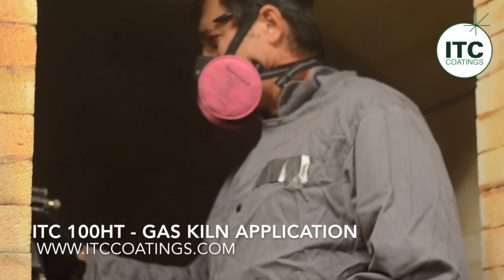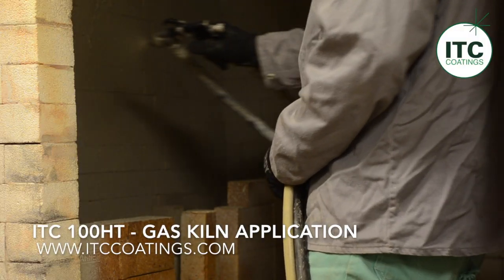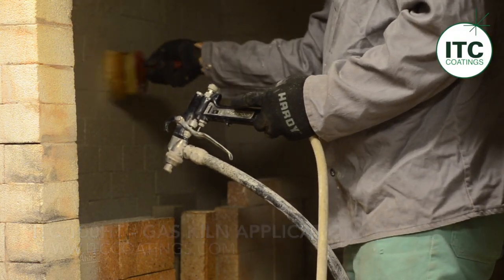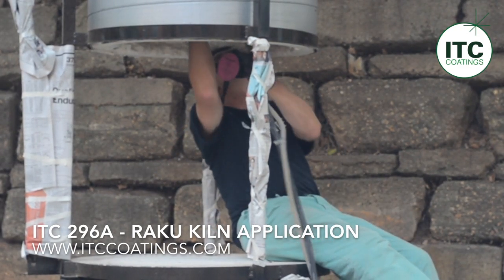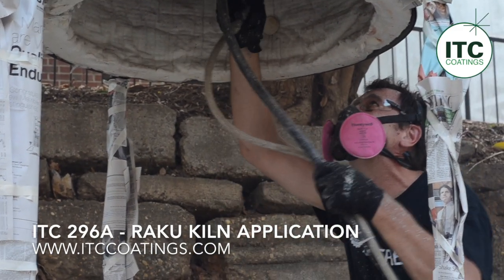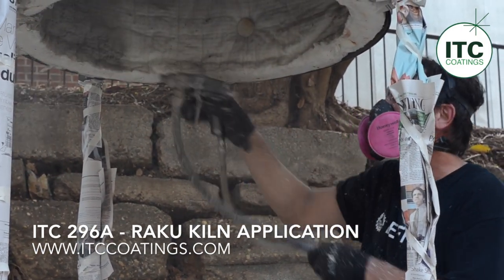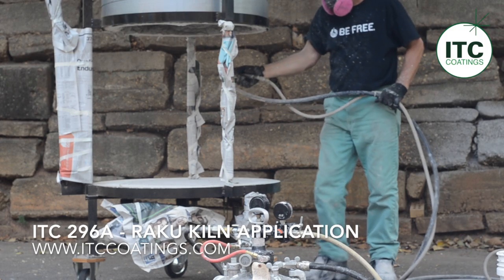The preferred method of application is to spray the coatings onto the substrate using a commercially available textured drywall hopper spray gun. In the application shown here in this video, I am using a Binks two-gallon pressure pot spraying rig. Square-foot coverage rates are 50 to 100 square feet per gallon of ITC 100HT and 100 to 200 square feet per gallon of ITC 296A. Once cured, ITC products produce a very hard protective surface over soft friable refractories such as insulating firebricks, IFBs, and ceramic fiber blankets. ITC coatings produce cleaner operating environments in kilns and furnaces, resulting in higher temperatures, lower fuel consumption, and shorter process times.